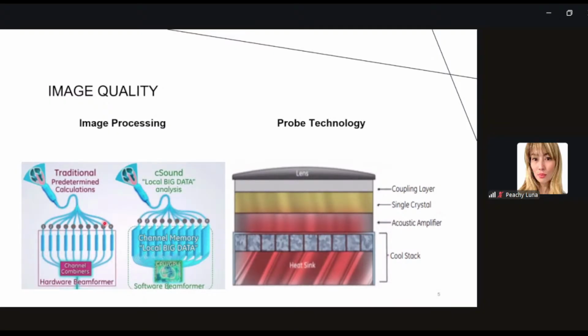Traditionally, the processors used to be hardware processing channels, receiving the sound waves or the beam from the probe, then into the processing channels, and then to be constrained into the hardware beamformer to produce the scanned images. Currently, with the development of the digital channels, we're now able to receive large data coming from the probe into the unlimited channel memory to be then stored and recombined with a software beamformer right here. This provides enhanced contrast and spatial resolution in the images.